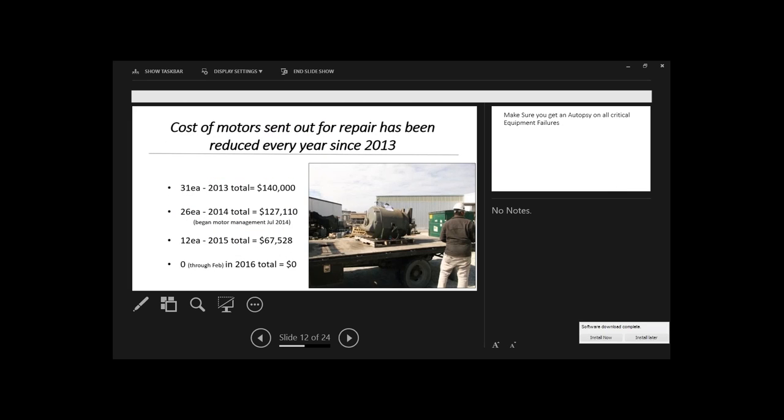So it's really come a long way in the last year and a half. We're really making some good progress on lube storage and lube cleanliness. As you'll see in a little bit, some of our savings and some of our justification for the program allowed us to purchase a lube storage building, transitioning to where all of our lubrication will be stored indoors in a controlled environment. We'll have the ability to filter the oil as we receive it. Drums are both circulated through some filters while we're storing it, and then also filter it as we dispense it. The cleanliness levels are coming up, accrued a whole lot in the last six months to a year.